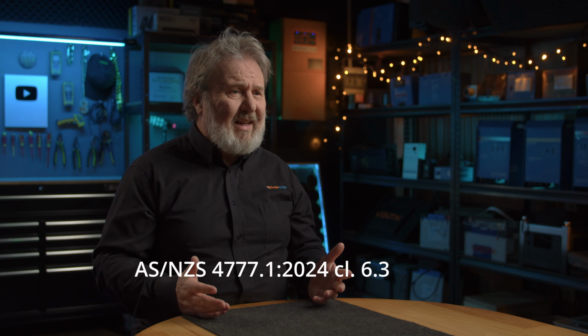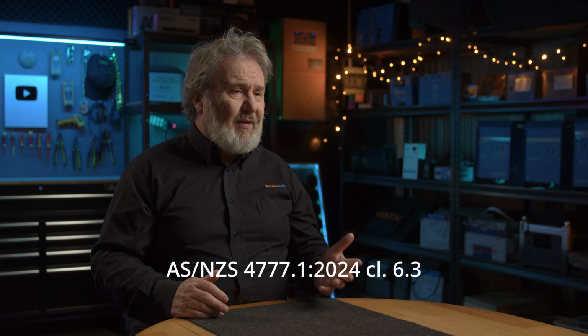In fact, 4777 Part 1 doesn't even mandate a colour in clause 6.3 for main switches or their labels. So there are many ways to distinguish a main switch from other switchgear, such as the switch colour itself. You know, it's quite common to see a red toggle. Its position on the switchboard, typically grouped on the left-hand side. That's pretty popular. Spacing from other switchgear, or using a coloured main switch label, such as those shown in 4777 Part 1. I think you'll find quite a lot of the label companies will defer to that option.